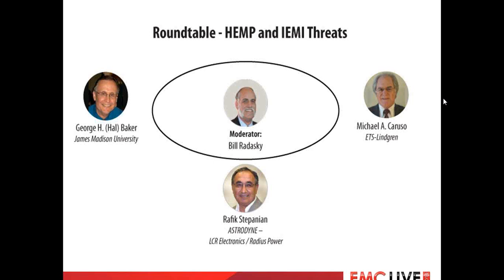There were tests at Oak Ridge National Lab of distribution transformers—they tested around 20 transformers—and found that transformers with inherent lightning protection right on the terminals tended to be immune from the fast EMP pulses. So there's good reason to believe that MOV devices on your transformers may help protect against EMP overvoltages. But in general those are not sufficient, because EMP is much faster, with much faster rise time—nanoseconds versus microseconds—than lightning.